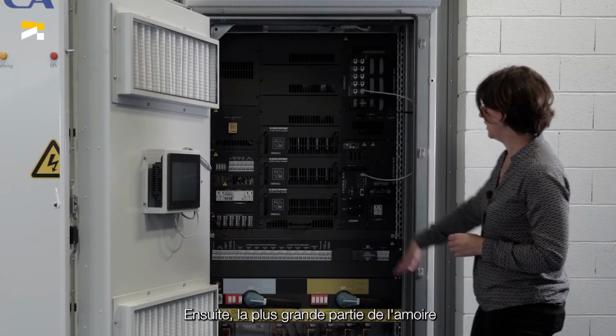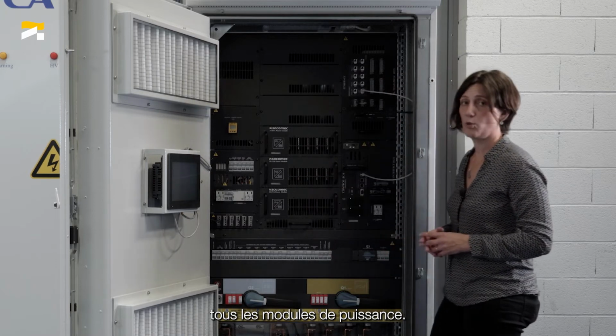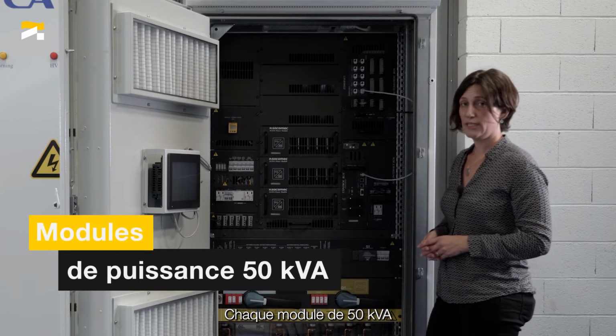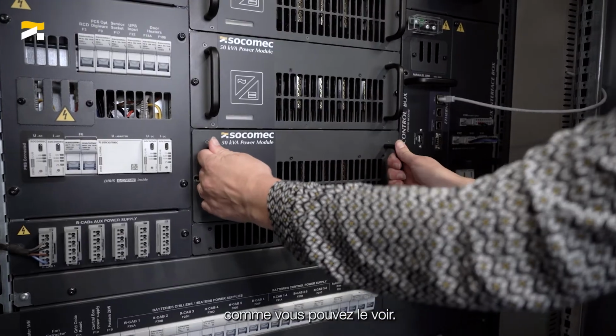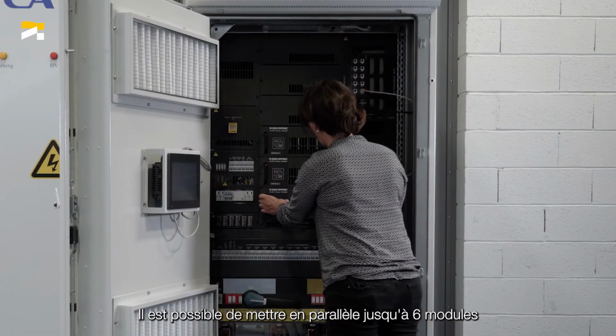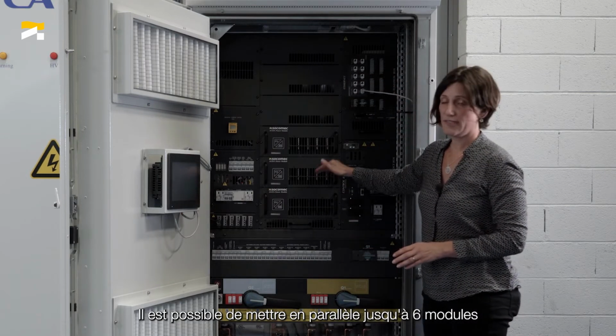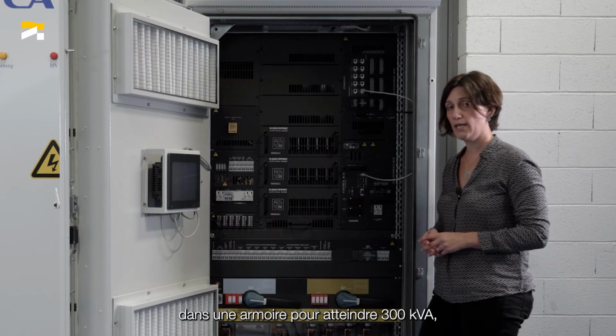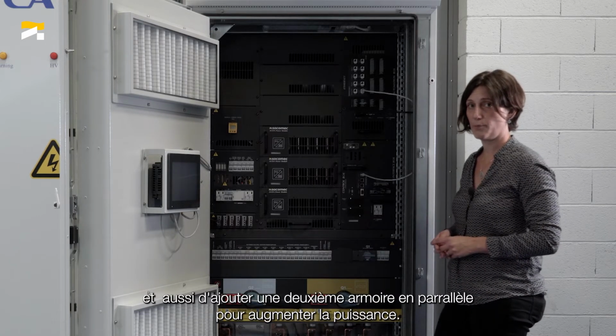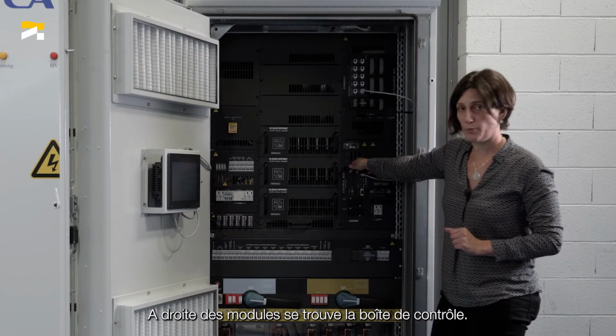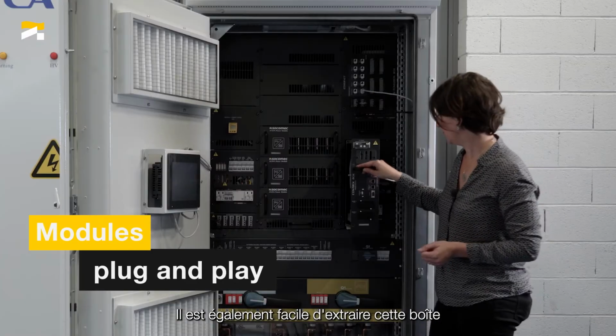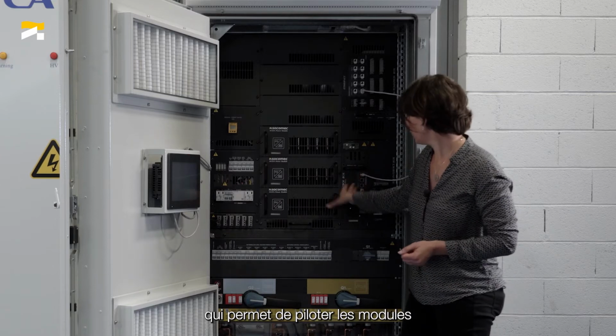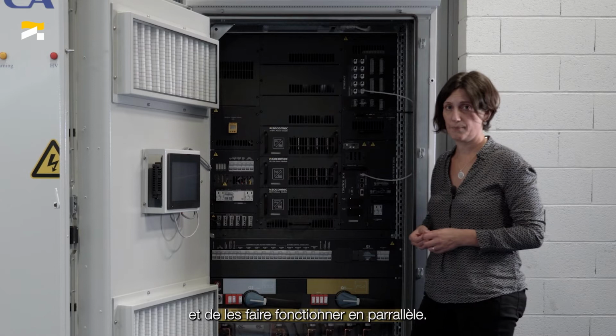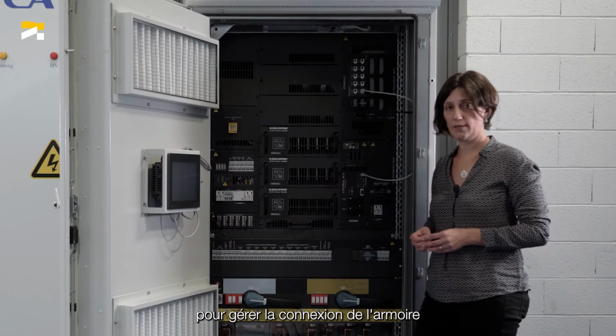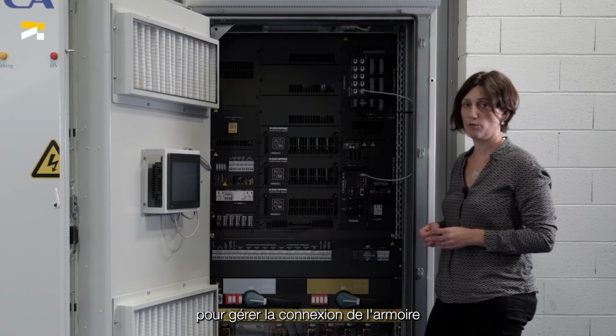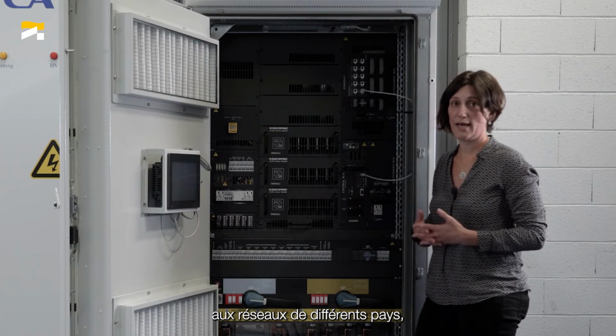Then, the biggest part of this cabinet is in the center, right here, where we have all the power modules. Each module is 50 kVA and can be easily withdrawn. So, as you can see, in one cabinet, we can put up to 6 modules in parallel, reaching then 300 kVA, and we can add a second cabinet in parallel to reach higher power. On the right of the modules is the control box. Again, you can easily withdraw this box. And this box is there to pilot all of the modules and to make them operate in parallel. Inside this box, we also have the grid code board that will enable the connection of the cabinet to different grids in different countries as expected by customers.